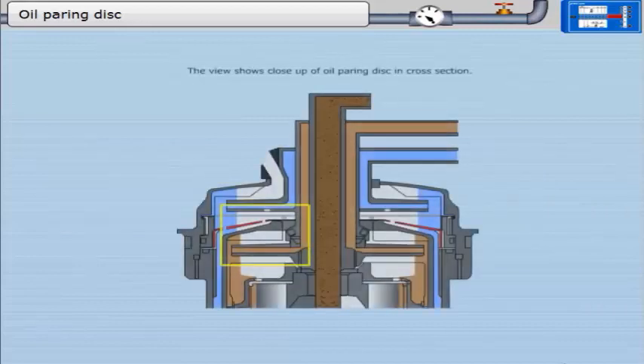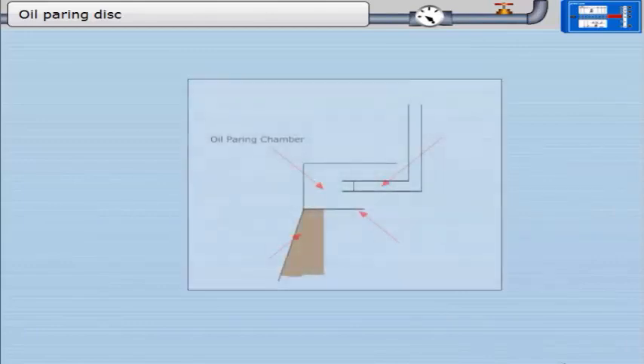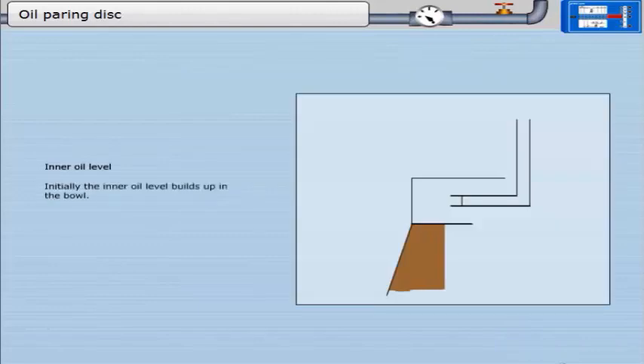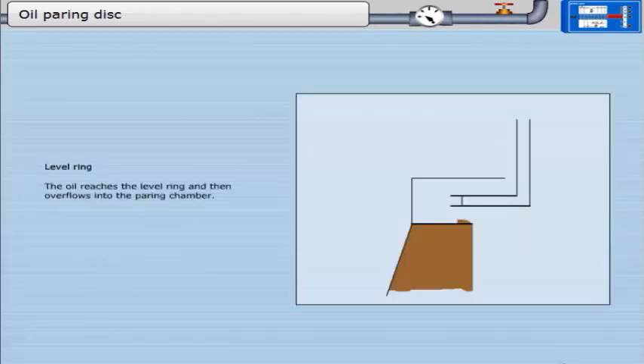The view shows a close-up of the oil paring disc in cross section. Initially, the inner oil level builds up in the bowl. The oil reaches the level ring and then overflows into the paring chamber. The level ring determines the position of the inner oil level in the bowl.